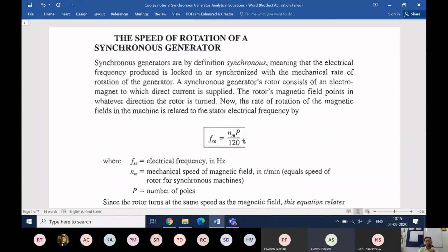RPM, right? So that's why, if you go back and refer to the notes which I shared with you yesterday on Teams, you'll find that that is also the reason why hydroelectric generators always have a large number of poles, so as to bring down the synchronous speed at which it is operating, because frequency you cannot play around with. And you might recall, we discussed earlier that the hydro generators will have their speed in the range of 80 RPM to 1000 RPM. So therefore, they will have a large number of poles.